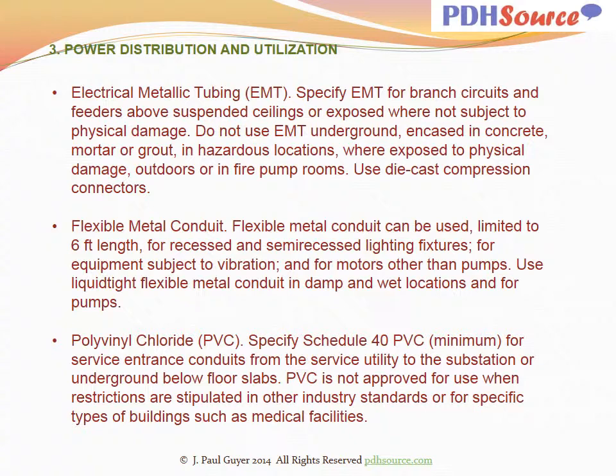Flexible metal conduit can be used, limited to 6 foot length, for recessed and semi-recessed lighting fixtures, for equipment subject to vibration, and for motors other than pumps. Use liquid tight flexible metal conduit in damp and wet locations and for pumps.